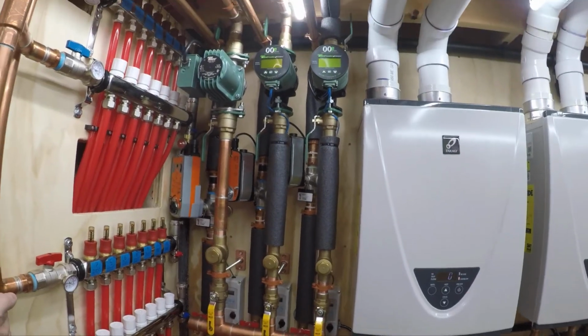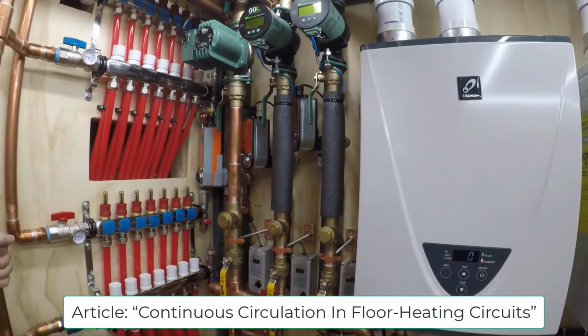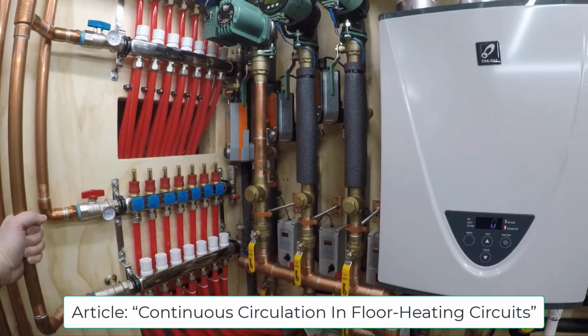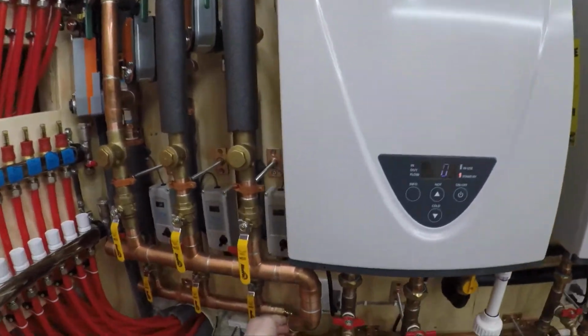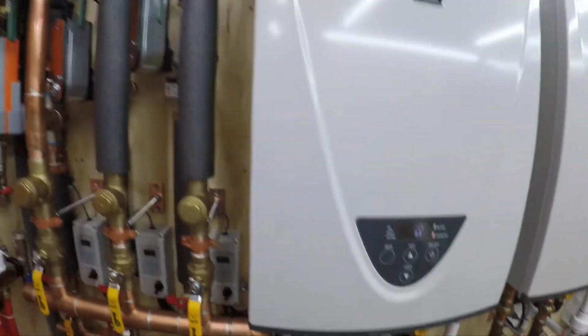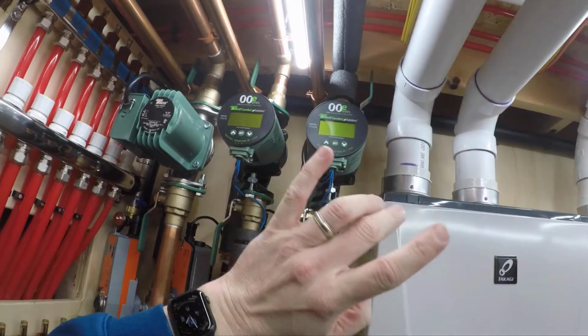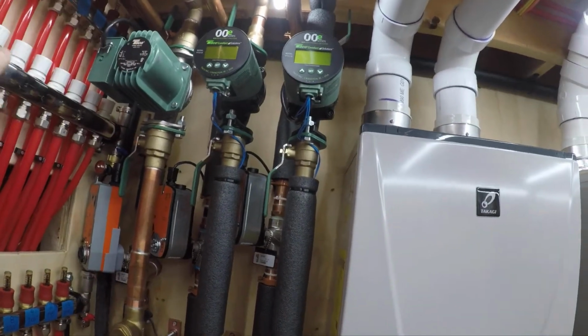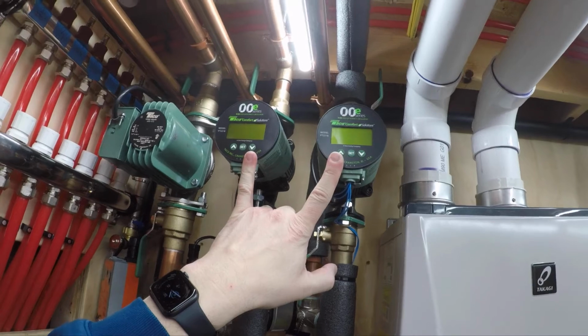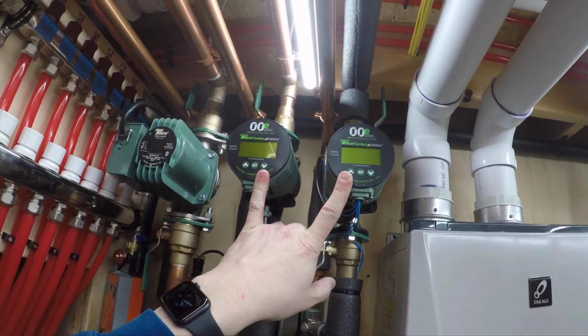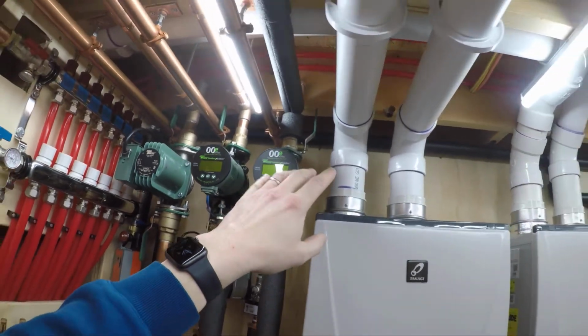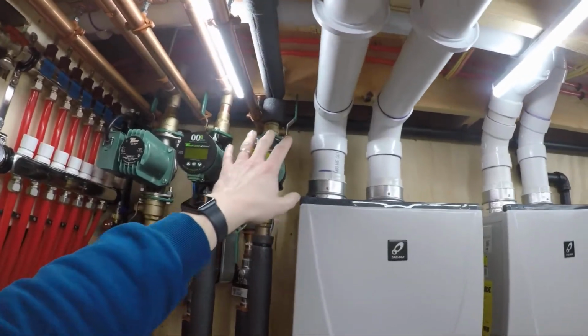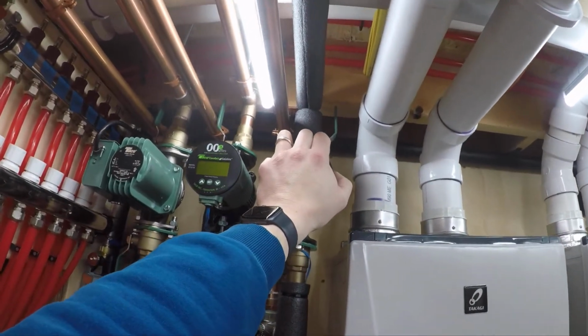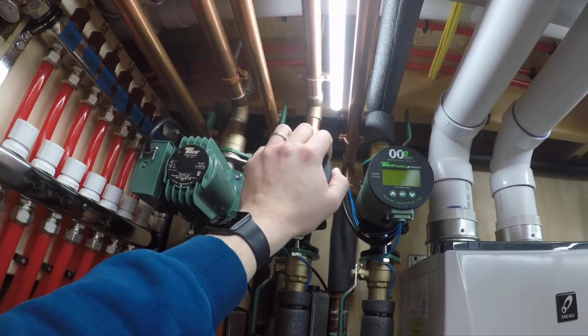So the article I read came up with this whole concept of continuous circulation. And what you do is, whenever the radiant is on, these pumps run nonstop. They run continuous. Now, these are Delta T pumps. They're these Viridian VT 2218 pumps. So I set the Delta T I want on them, which for the staple up is like 10 degrees, and for the slabs it's like 20.